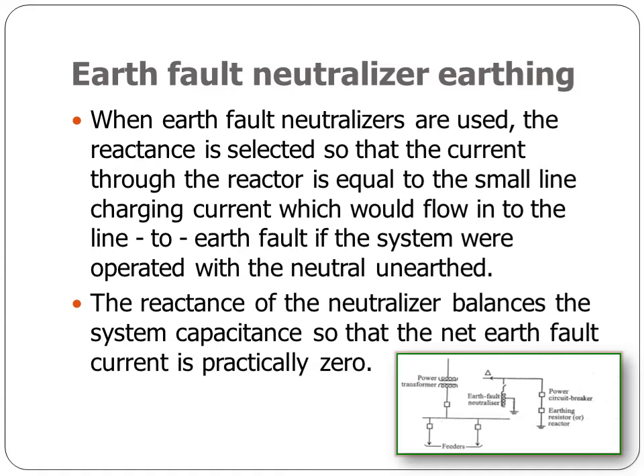Earth fault neutralizer earthing. In this method, when the earth fault neutralizer is used, the reactance is selected so that the current through the reactor is equal to the line charging current which would flow into the line to earth fault. The reactance of the neutralizer balances the system capacitance so that the net earth fault current is practically zero. The diagram indicates the feeder lines, the power transformer, and the earth fault neutralizer.